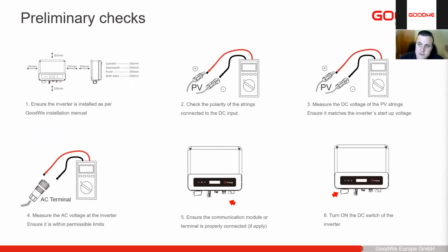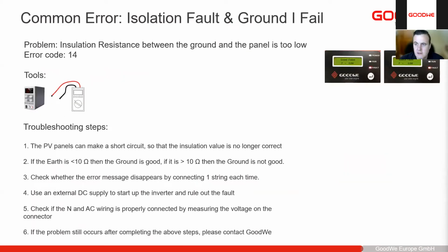It's obviously always good to do preliminary checks for our devices just to make sure that our polarity and everything is correct. So one of our most common faults is isolation fault or ground I fail. This is where the insulation resistance between the ground and the panels is too low.